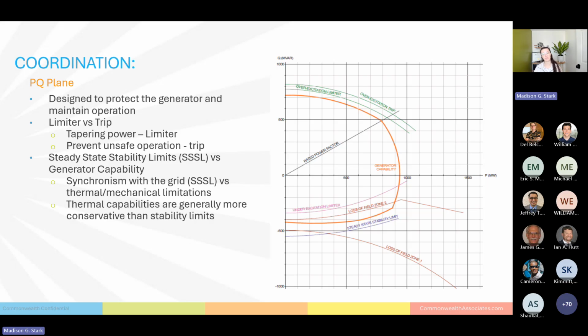The next thing we're going to hit is our overexcitation limiter. Also good. What that means is that as we exceed our generator's capabilities, the limiter is going to push it back down to maintain a stable steady state operation. The reason you see the limiter on the far side of the capabilities is that in fault conditions, this generator needs to be able to push additional power. So having this limiter just outside those capabilities means that the generator can respond in fault conditions to help restore stability to the grid.